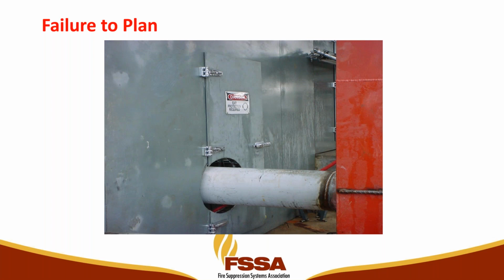There was an interesting conversation yesterday on EPRI. Safety Council is trying to write some standards as well, and FM got involved in the conversation. What they want to do is show that a module didn't propagate, didn't catch fire, but it produced gas. So do you add an external ignition source to light that, with the assumption that maybe the batteries may not do it, but if there was a failure mode in the power supply or some other electrical component that could ignite that? I think you'll see that coming, that explosion hazard will be much more of an evaluation, both by FM and UL.